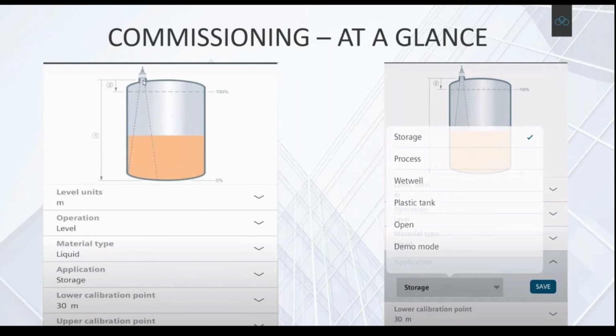The beauty is, even on the mobile app, if you change to solids, then you'll see another case where it's angled for solids, because solids won't always have a directly overhead or perpendicular radar positioning. For example, here on the right-hand side, is it just storage, or is it our process? Does that mean there's a flow out and flow in? Do we need to control flow in and flow out, make sure it's not emptying too quickly or filling too quickly?